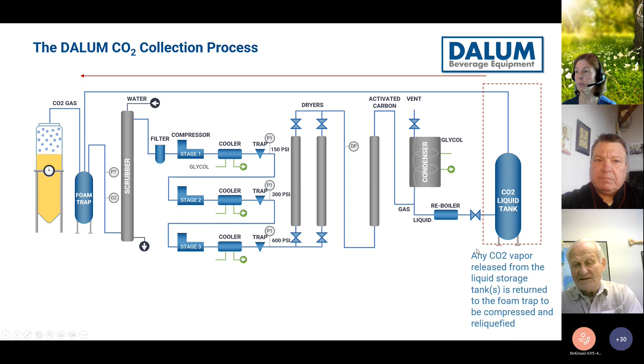Next slide. This is called a reboiler. What it is basically doing is heating up the liquid CO2 so it boils, so it bubbles, and that drives off more oxygen and nitrogen from the liquid itself. It gives us the ability to get down to very, very high purity of CO2. From there, we go to a CO2 liquid tank. And in our case, if there's any flash gas or any venting from the CO2 liquid tank, that goes back over to the foam trap and we recondense it. So it's basically no losses there from the venting of the liquid CO2 tank.